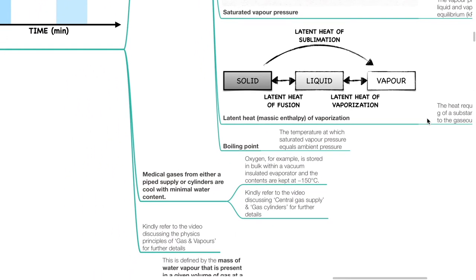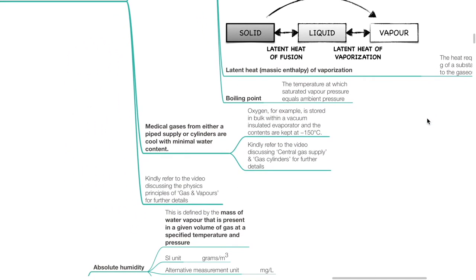Medical gases from either a pipe supply or cylinders are cool with minimal water content. Oxygen, for example, is stored in bulk within a vacuum insulated evaporator and the contents are kept at negative 150 degrees Celsius. Refer to the video discussing central gas supply, gas cylinders and gas and vapors for further details.